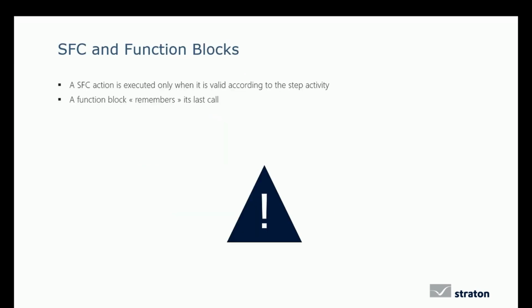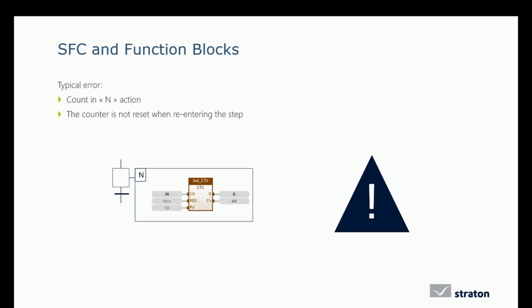It is possible to use function blocks in SFC, but note that an SFC action is executed only when it is valid according to the step activity, and a function block remembers its last call. For example, a typical error is to use a counter block that counts in the N action. The counter is not reset when re-entering the step, so if the counter had the value x when leaving the step, it will still have the value x when re-entering the step.